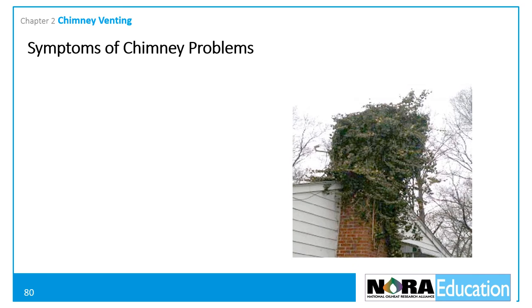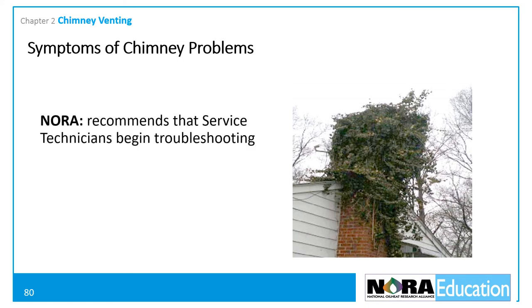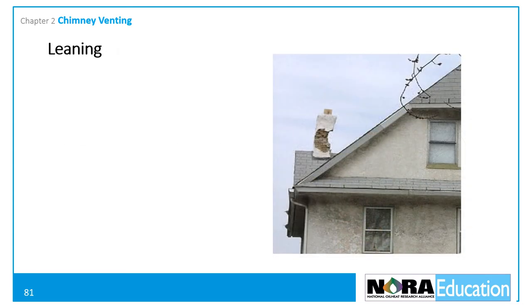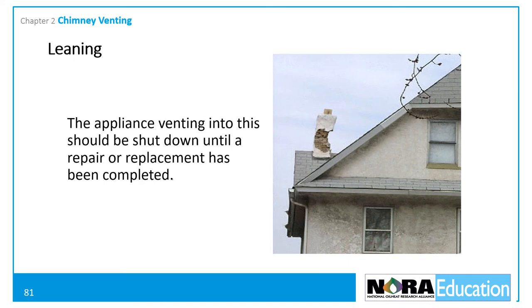There are a number of tell-tale signs that indicate a chimney is in need of repair or relining. NORA recommends that service technicians begin troubleshooting before they enter a customer's home or business. As a technician approaches a job site, he or she should look at the chimney for any indications of a problem. Once inside, the inspection should continue. Among the more common indications is leaning — a chimney that is clearly leaning is in need of major repair, and the appliance venting into it should be shut down until repair or replacement is completed.